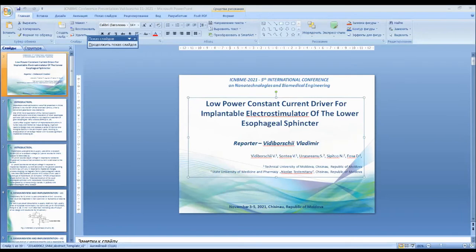At the same time, the traditional stimulators are relatively big devices, and usually they use batteries to store energy, and have implantable electrodes. And from this part also begins something interesting, because if you have a foreign body in your organism, it begins to react, and this could result in encapsulation and a change in impedance. So that's why implantable stimulators usually use different types of modulation via constant current or constant voltage.